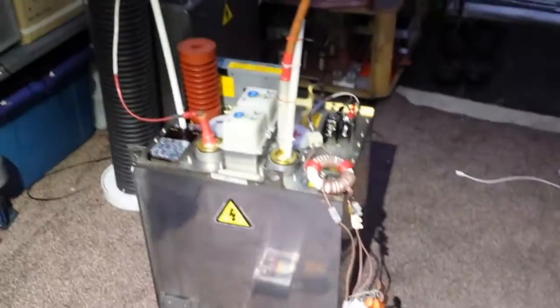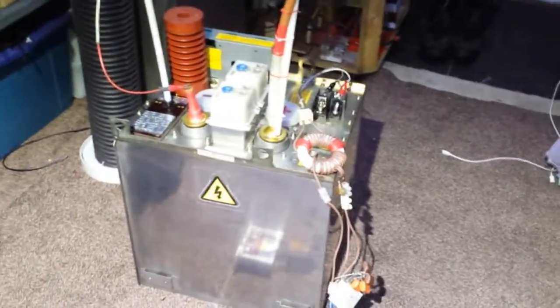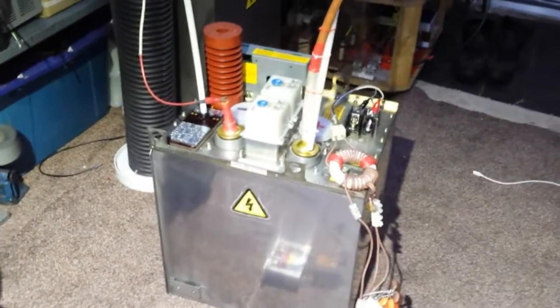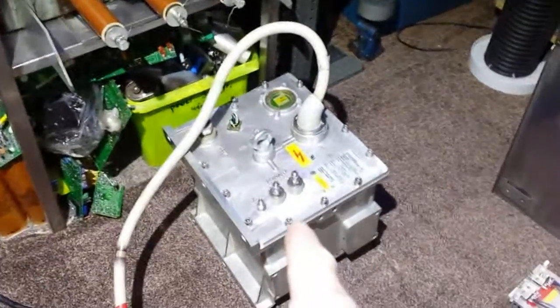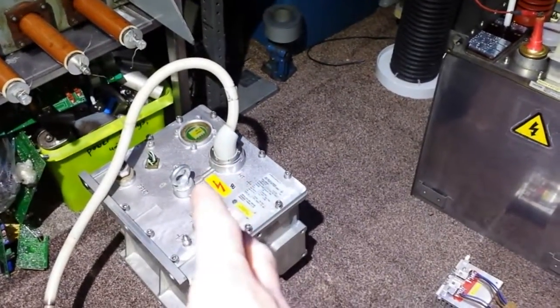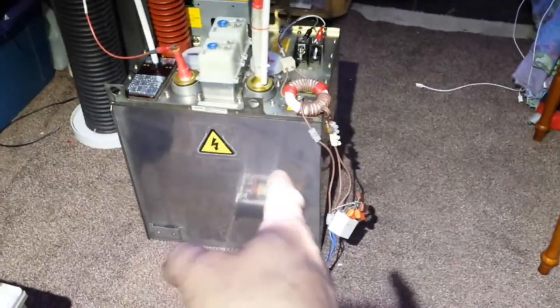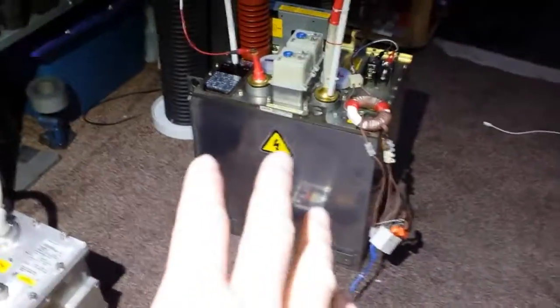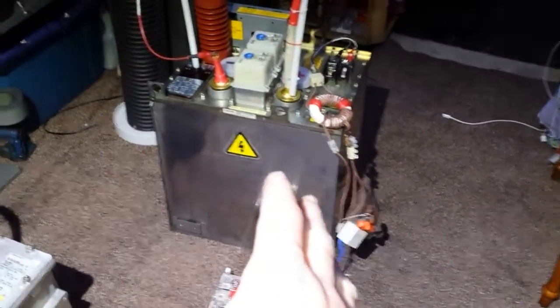This one when energized will pull 20 odd amps at 40 volts. Of course that's 150 kV and this one's 70 kV, completely different. That's not as much milliamp out as one of these. These are 100 up to 400 milliamps depending on the actual transformers themselves.